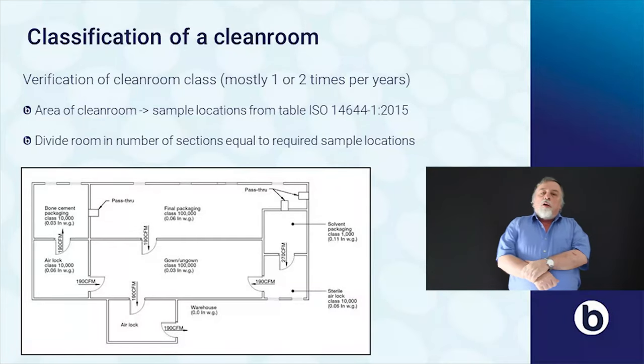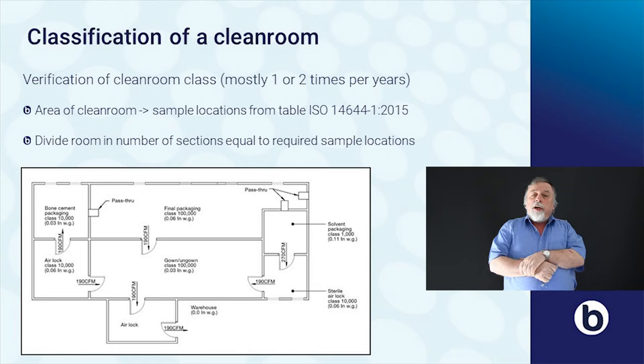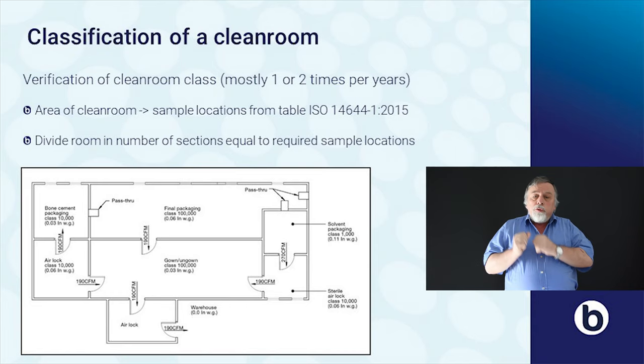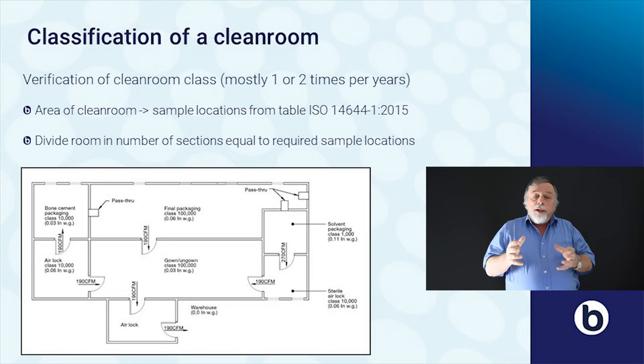We can talk about the total number of particles larger than 1 micrometer. When we want to classify a clean room, we have to follow a procedure written in ISO standard 14644-1, published in 2015. The starting point is the area of your clean room in square meters. You go to the table in the standard, which gives you the number of sample locations required. Then you divide the room into sections equal to the required sample locations, and determine one measurement point in each section.